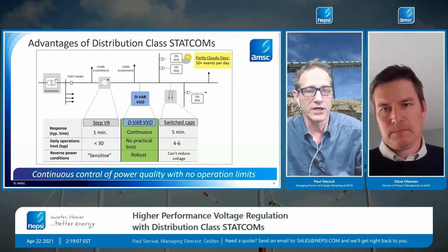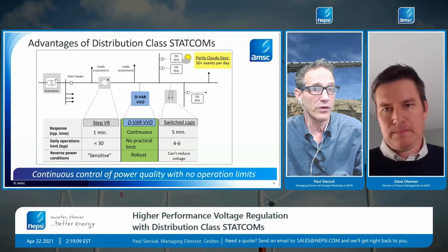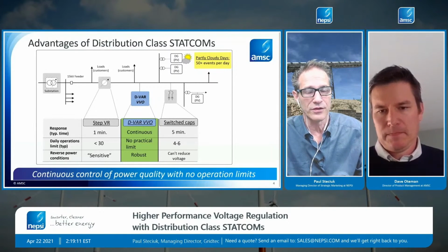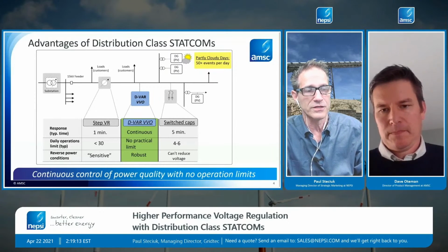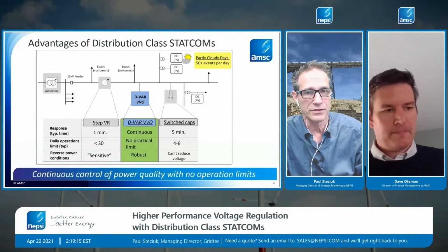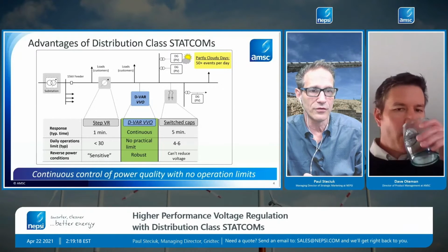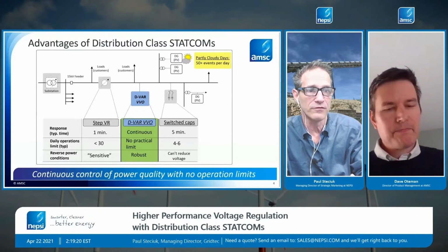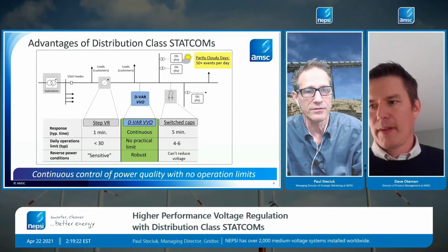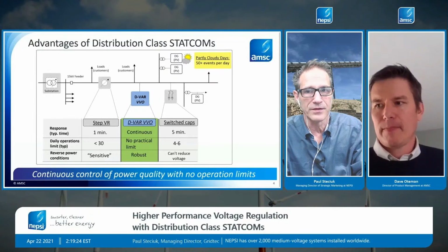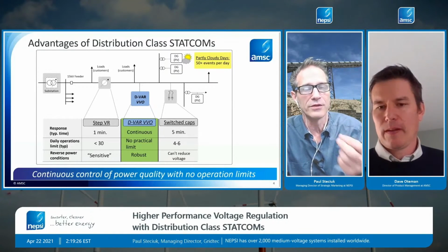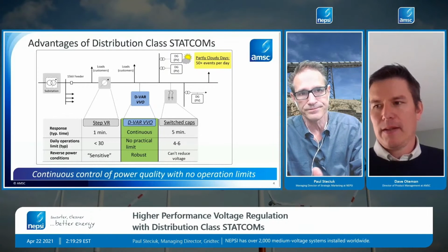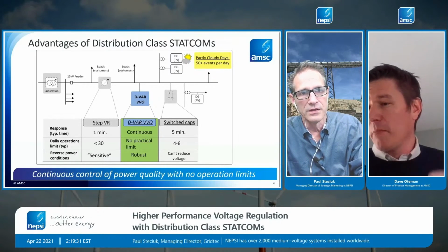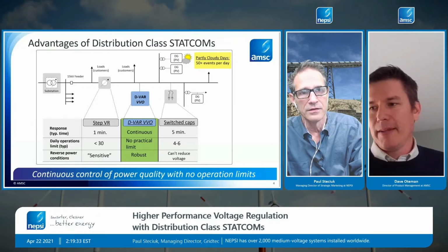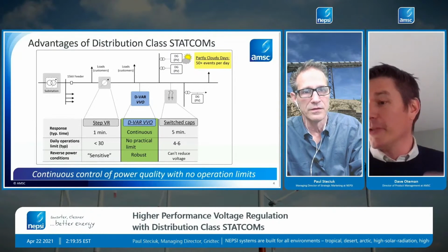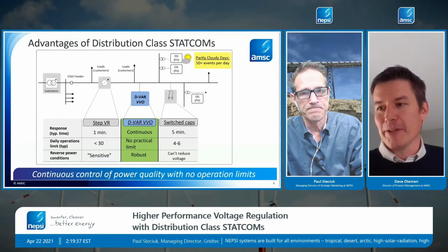So those switching operations could quickly wear out a capacitor bank if they were to set the control such that it was constantly controlling based on voltage. And the same holds true for the voltage regulators. Same exact concept, you can only have a limited number of switching operations. Yep, and a line regulator will typically have more than a cap bank, but not to the extent where it addresses this limitation sufficiently.